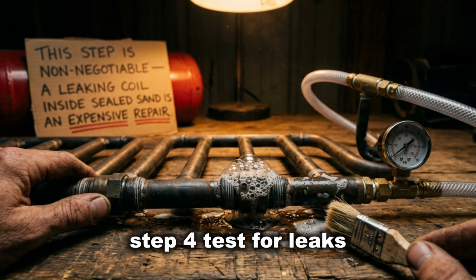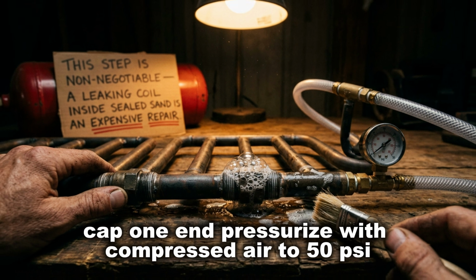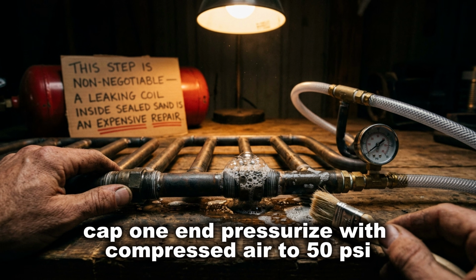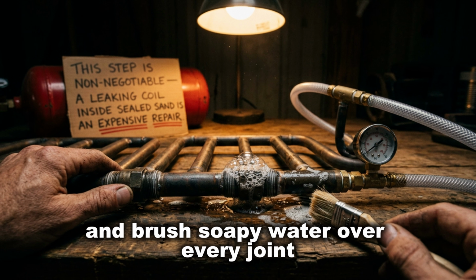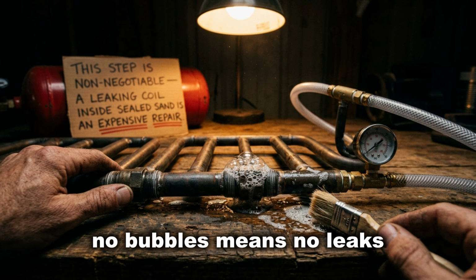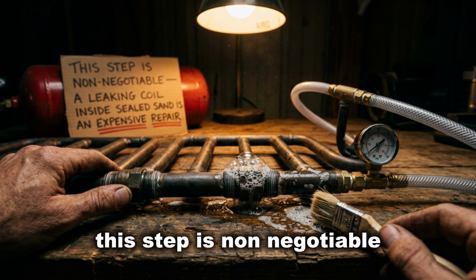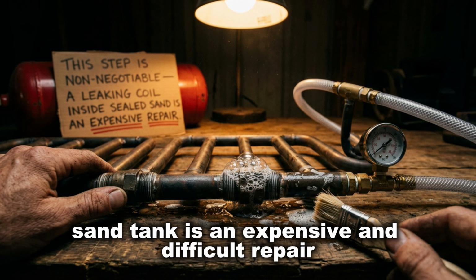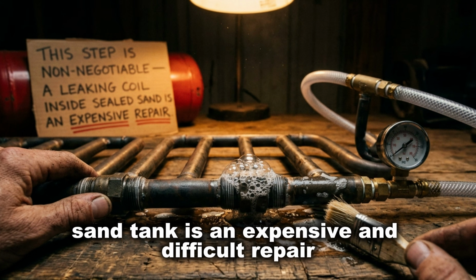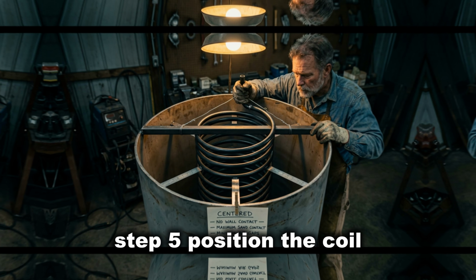Step 4. Test for leaks. Cap one end, pressurize with compressed air to 50 psi, and brush soapy water over every joint. No bubbles means no leaks. This step is non-negotiable. A leaking coil inside a sealed sand tank is an expensive and difficult repair after the sand is in place. Step 5.